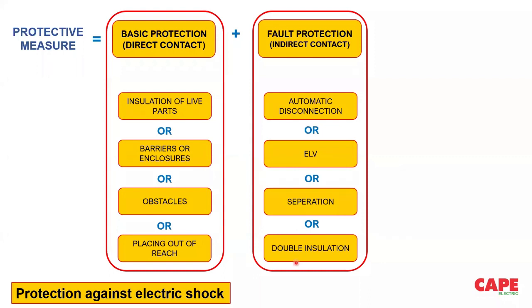For example, in our last webinar regarding solar PV, we discussed a lot about double insulation. In a solar PV, especially on the DC side, protective devices for quick automatic disconnection are not available. For example, fuses are not efficient enough to quickly disconnect. MCBs are not efficient enough to quickly disconnect the supply in case of a fault. There is no ELCB or RCD available. They are still under development. There is no arc fault detection device, AFDD, for pure DC application. So basically, disconnecting the supply during a fault is very difficult.